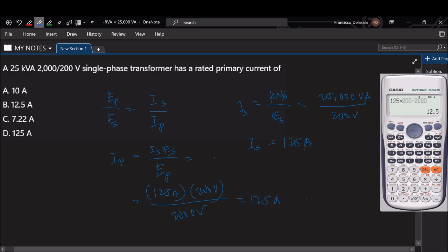So that's 12.5 amperes. There's also a shortcut: primary current is just equal to the VA divided by the primary voltage. So 25,000 divided by 2,000, and our primary current will just be the same, 12.5 amperes, which is letter B.